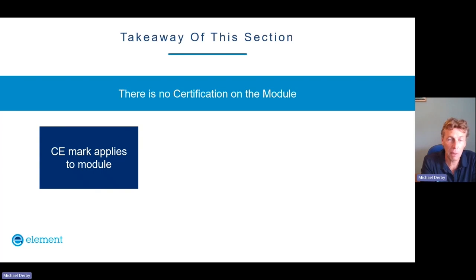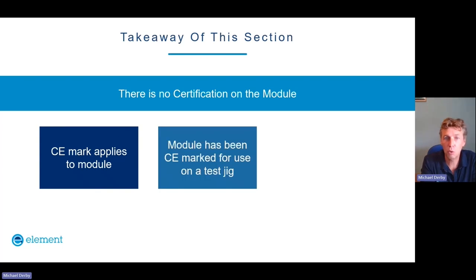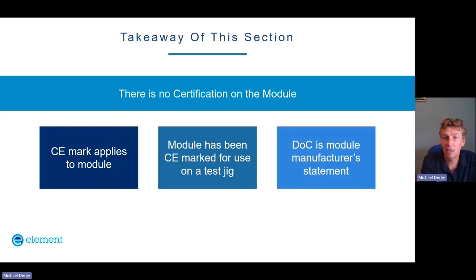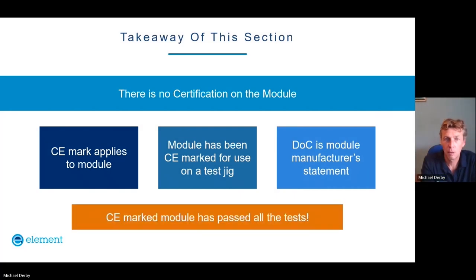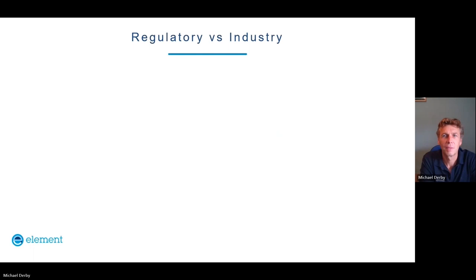The CE mark applies to the module. The module has been CE marked, usually for sitting on a test jig, and the DOC is the module manufacturer's statement that it did comply in that configuration. But good news, the CE marked module has fully passed all the tests.